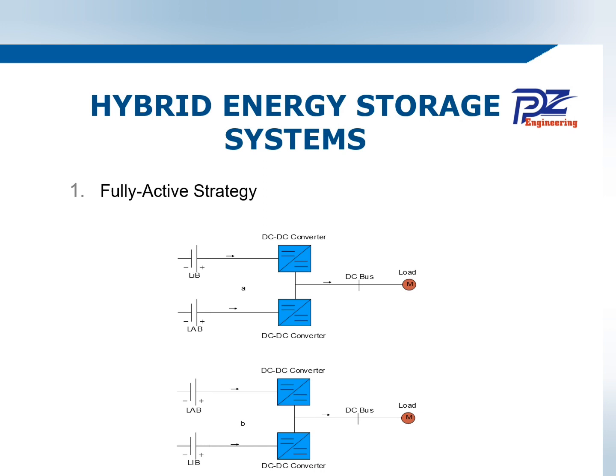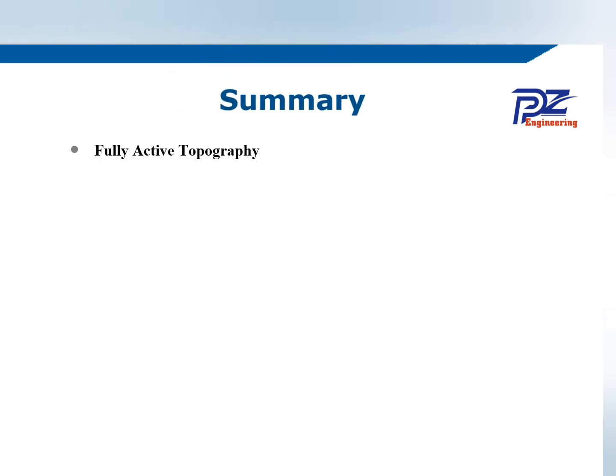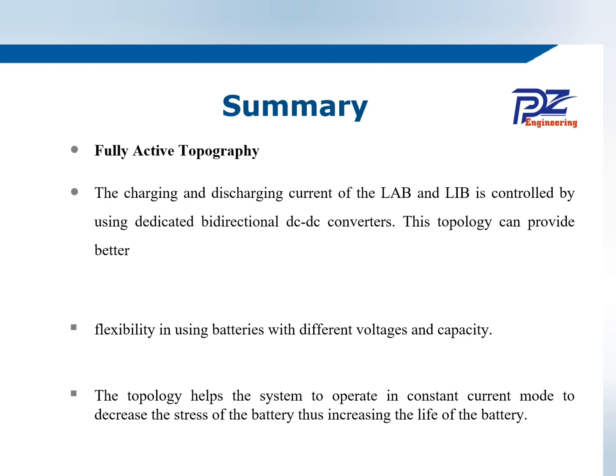As a summary, the full active topology has the advantage compared to others. The charging and discharging current of the lead-acid and lithium-ion batteries is controlled by using dedicated bidirectional DC-DC converters. This topology can provide better energy strength and flexibility in using batteries with different voltage and capacity. It also helps the system to operate in constant current mode to decrease battery stress, increasing the lifespan.